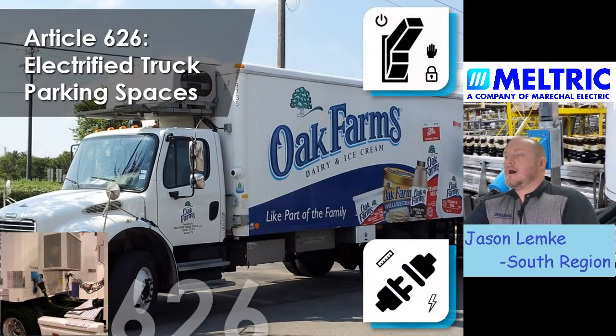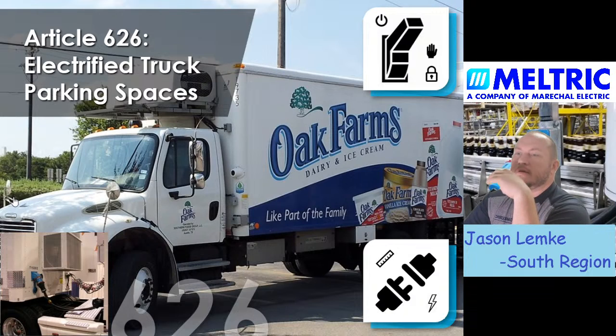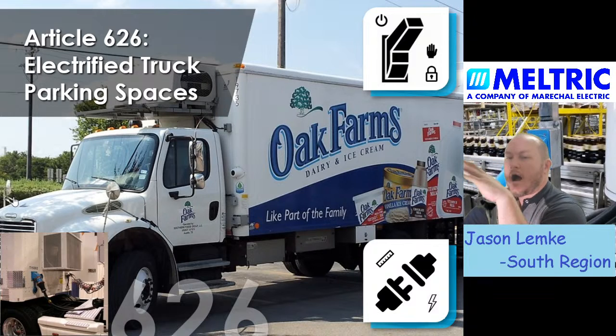So let's go back to one other thing real quick, where we're going to talk about now, because we've gone through where you might use a switch-rated plug-in receptacle. Let's talk a little bit about why you might want to use a switch-rated plug-in receptacle. So obviously, when you have a plug-in receptacle that is going to be connected or disconnected while it is energized, you are probably going to want to have that device be switch-rated, particularly if the intended purpose of that device is to be the switch. You will want it to be switch-rated.